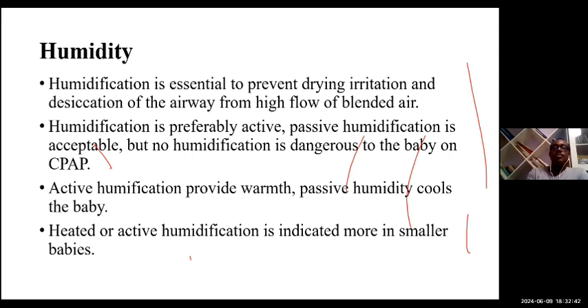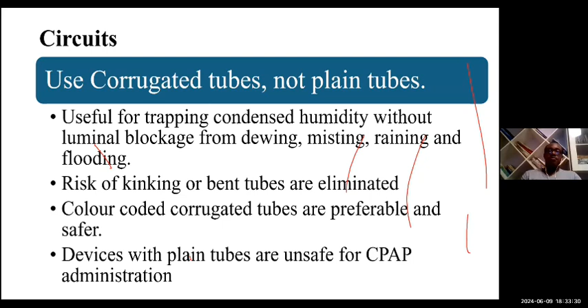So here we are looking at circuits. We need to use corrugated tubes, not plain tubes. And somebody will say, why? Because it's useful for trapping condensed humidity without luminal blockage. And you remember about the dewing of the tube, the misting, the raining, and the flooding. This can be very dangerous to the baby. It also prevents the risk of kinking or bending of the tubes. And if those tubes are color-coded, they are preferably safer. Devices with plain tubes are unsafe.